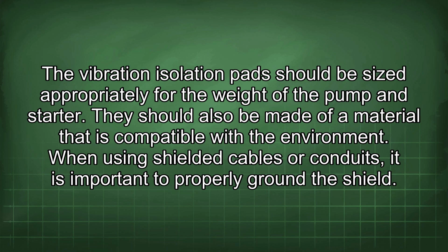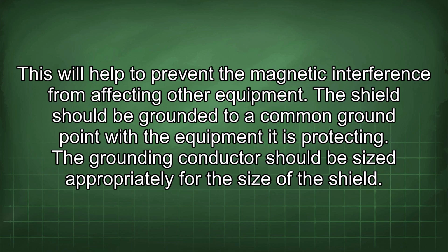When using shielded cables or conduits, it is important to properly ground the shield. This will help to prevent the magnetic interference from affecting other equipment. The shield should be grounded to a common ground point with the equipment it is protecting. The grounding conductor should be sized appropriately for the size of the shield.